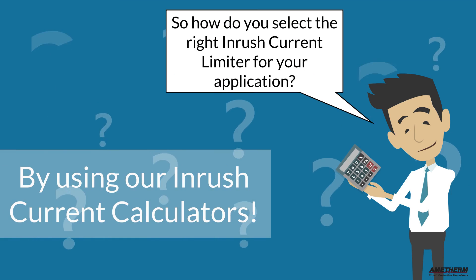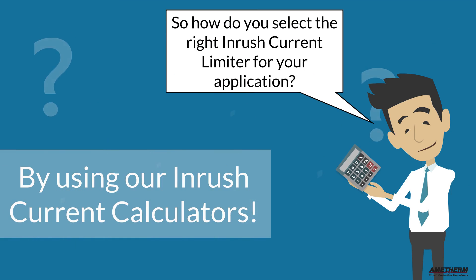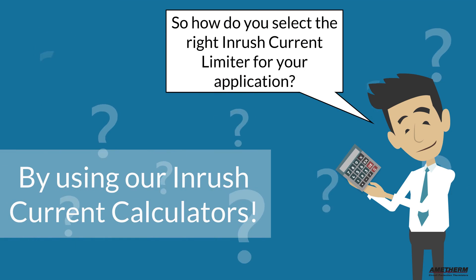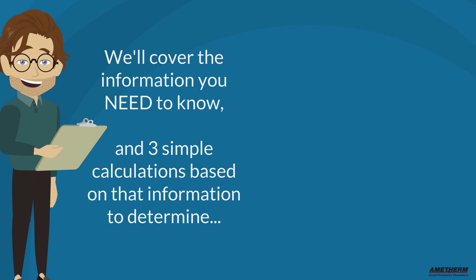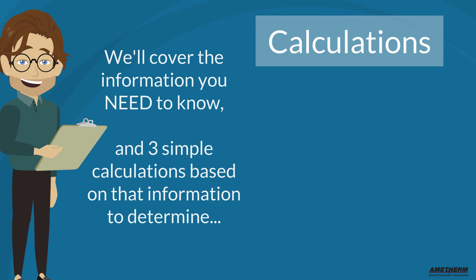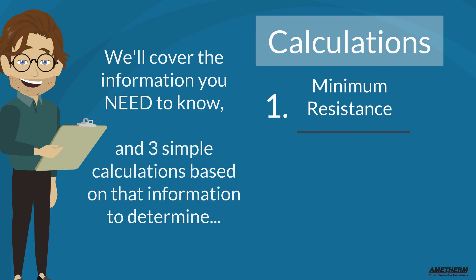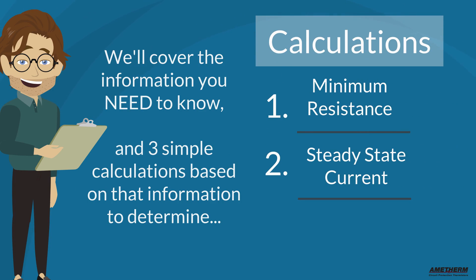Easy! Start by using our inrush current calculators. We'll cover the information that you need to know and three simple calculations based on that information to determine: one, the minimum resistance; two, the steady state current; and three, the maximum energy rating in joules.